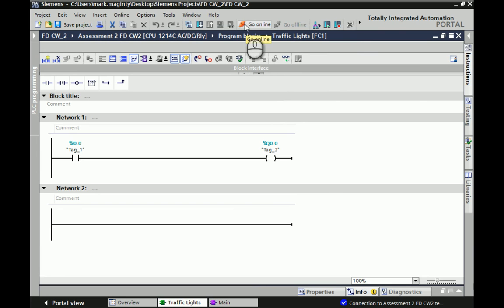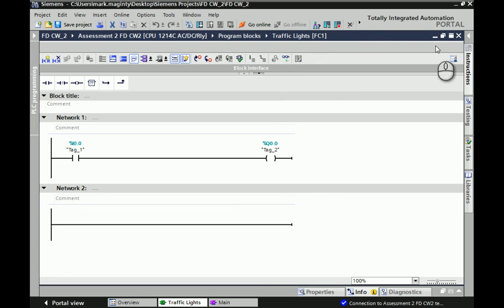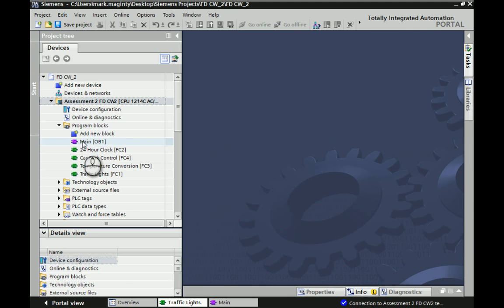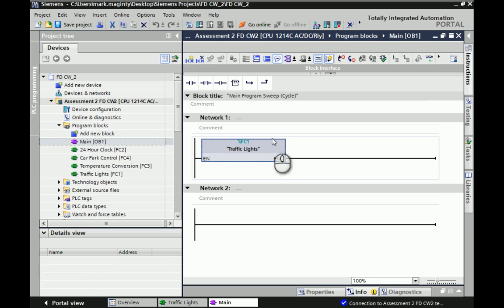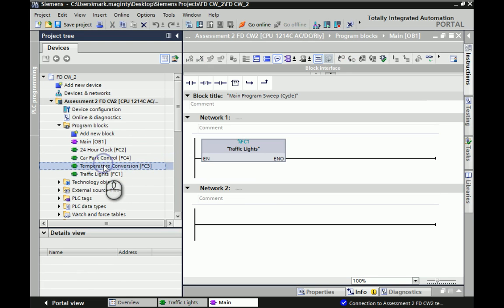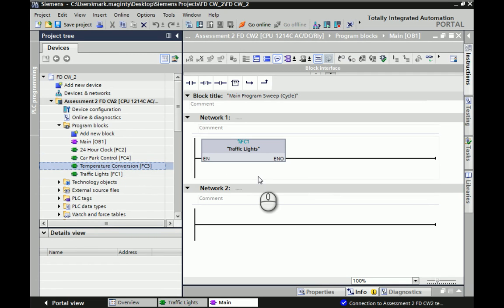You can go online and offline at the top up here as well. You can also test individual programs, or you can test multiple programs at the same time if you have them called via OB1. Currently, the only one we have is, if we have a quick look, we can nip back out and go to our project tree. If we open up main OB1, you see the only one we currently have called is FC1. Despite the fact that we have FC2, 4, and 3 created, none of them are actually running inside the PLC because they're not told to be active. Only the ones that are called within OB1, organizational block 1, will actually become active and run.